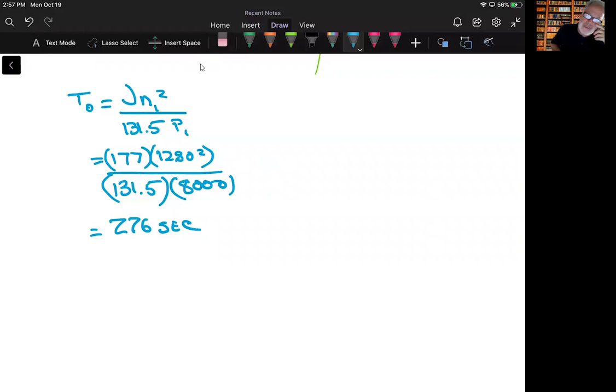So anyway, part C of this has us try to make the same determination without the braking resistor. The only portion we're looking at is basically the windage and friction losses. In other words, we're just letting it coast to a stop. In that case, if I plug this in here, I have to get a new half time constant. It comes out to be 276 seconds.